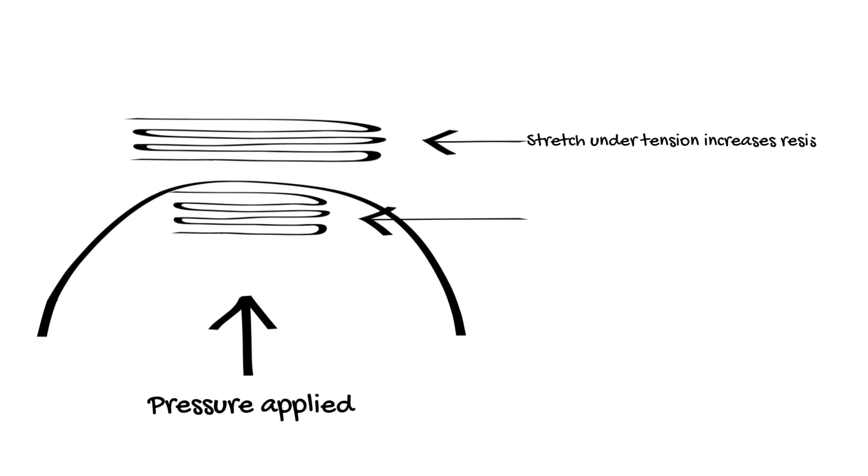As the strain gauge is stretched, the wire is drawn thinner which increases the electrical resistance. We can then measure this change in resistance and use it to calculate the pressure which is being applied to the diaphragm.